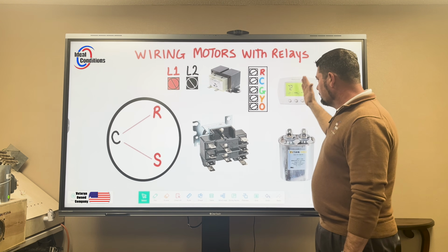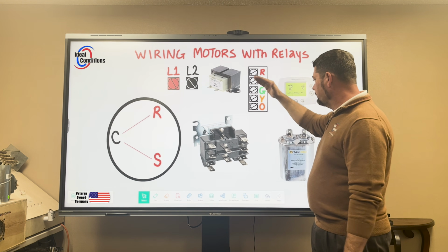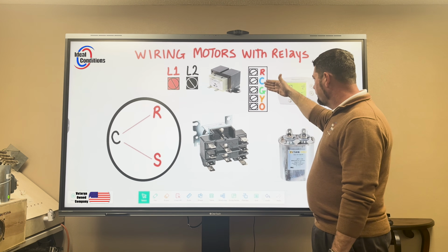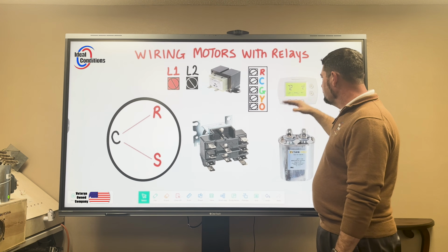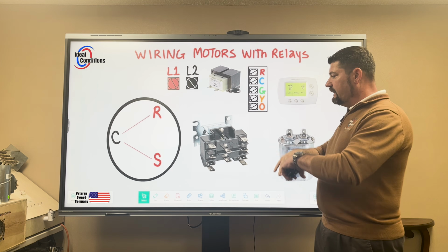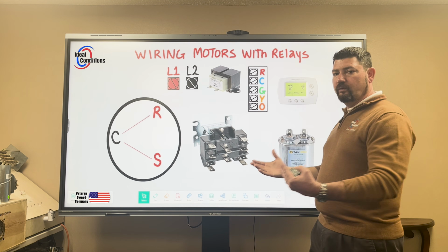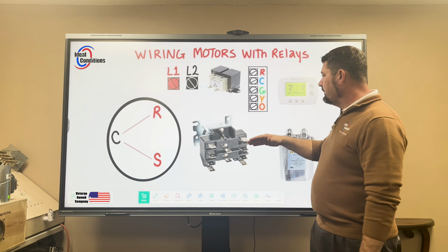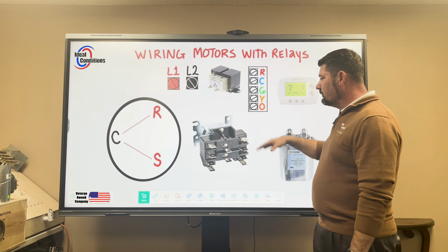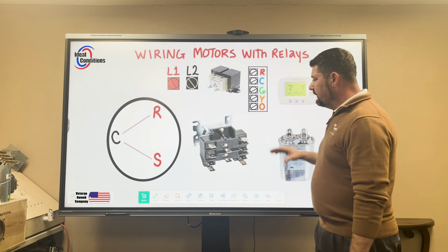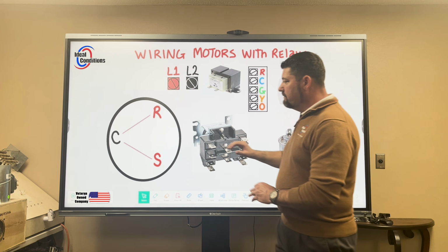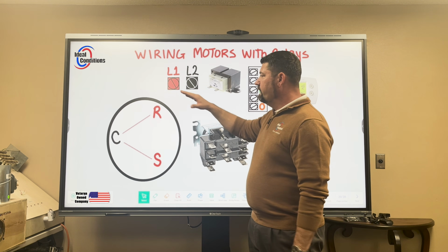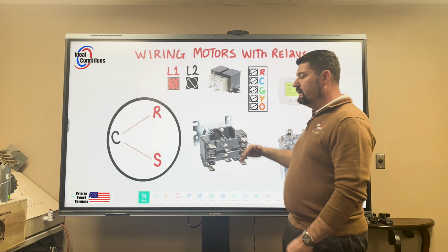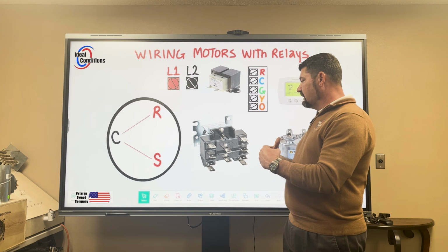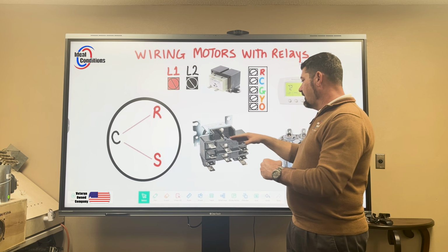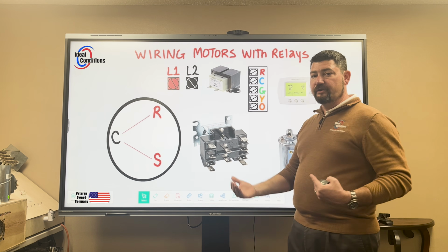We're integrating low voltage components, hence the transformer, the terminal block here, which is all low voltage, and the thermostat, just to help you understand your surroundings, where you're working at. We don't have heat strips up here, we don't have any W terminals, because our focus is getting the relay wired up and getting the motor to come on, and finding out where line voltage is present at all times, when the relay is in the off mode and contact voltage here is not being applied to the load, but how there's still power.